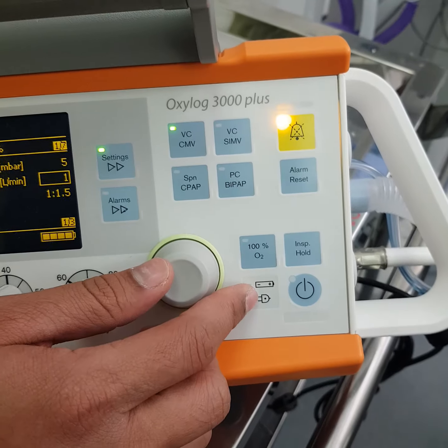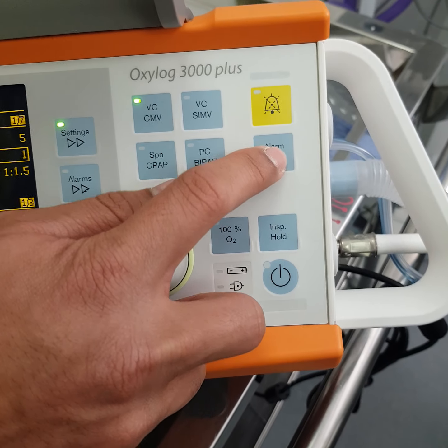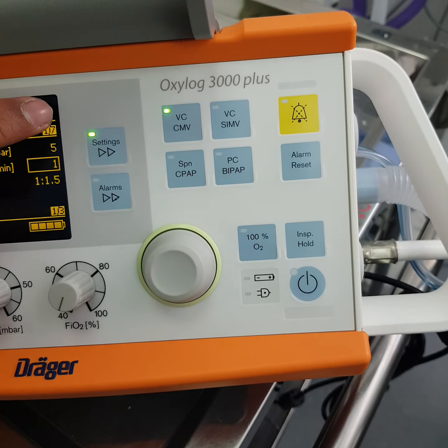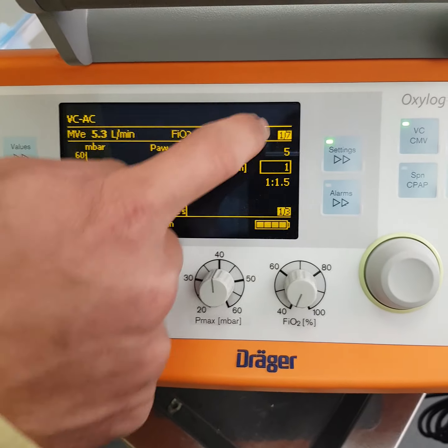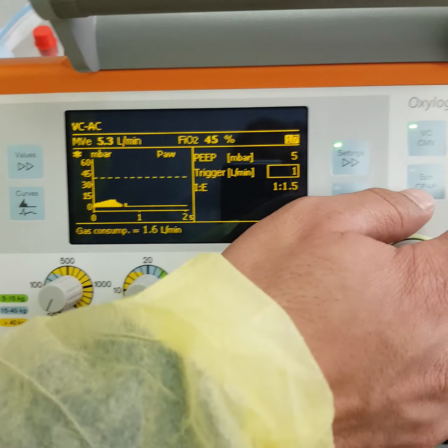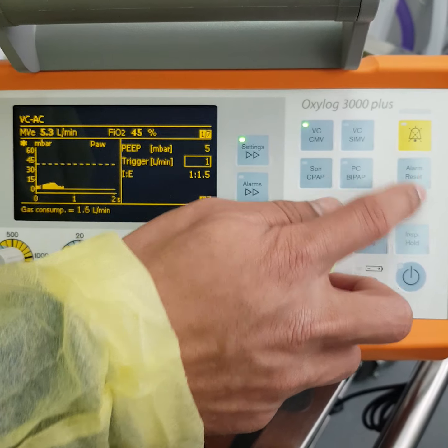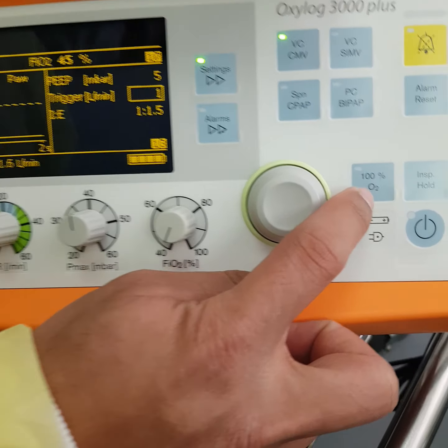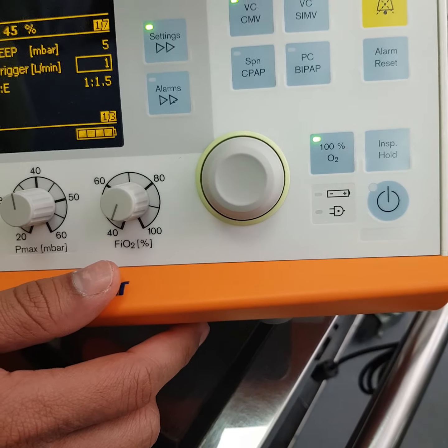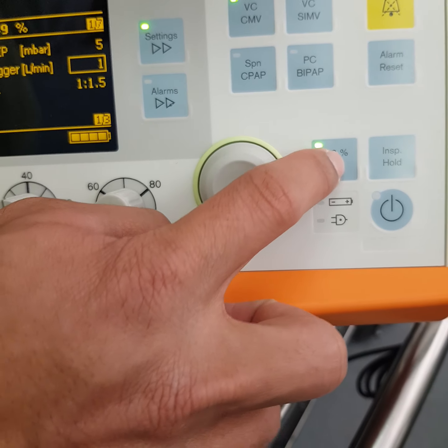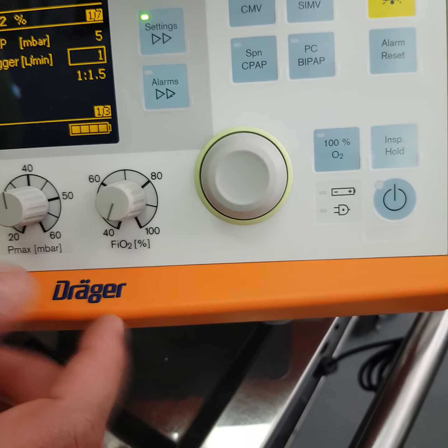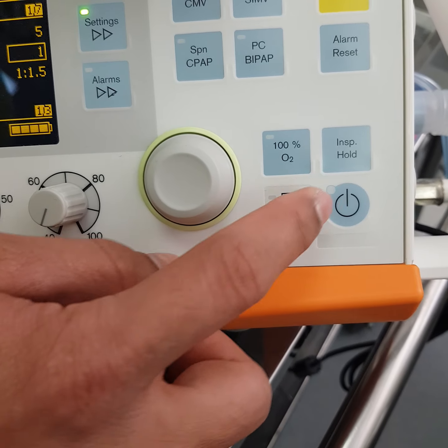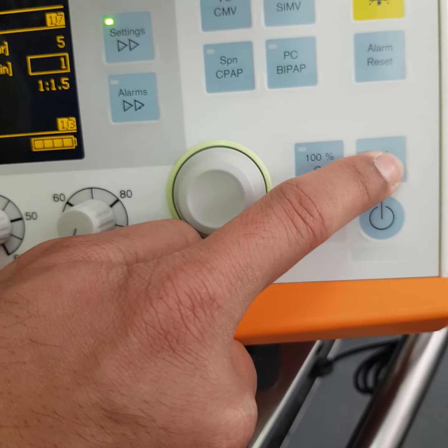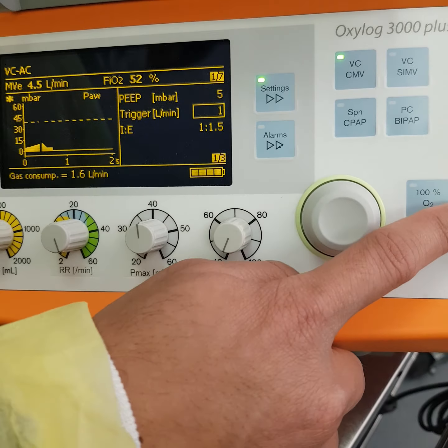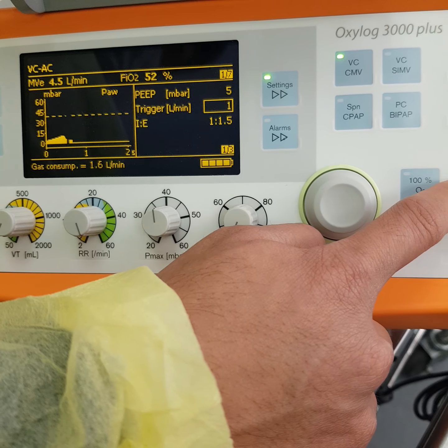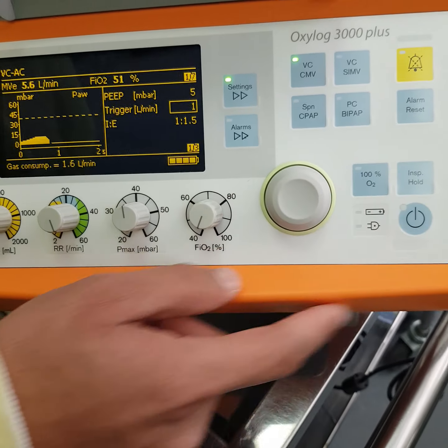This will silence the alarm for 2 minutes. And then there is the alarm reset button. If you have any messages on the screen over here, you can reset them by pressing the alarm reset option. And there is the 100% O2 button. If you want to do suctioning and so on, you can activate 100% O2 and do the suctioning for pre-oxygenation. Also there is inspiratory hold, if you want to recruit the lung or if you want to do an X-ray. For these kinds of purposes, this inspiratory hold can be used.